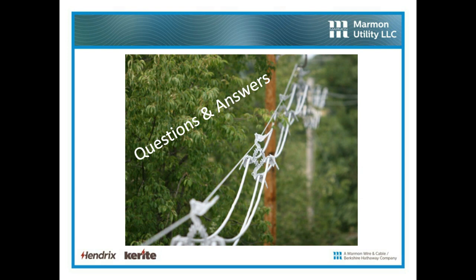Next question is, I've seen a tie wire cause the largest number of failures on bundled conductors. How has this been addressed with tie wire? With bare wire and covered conductor, I'd best have that one submitted in writing and give me a time to answer that. How has it been addressed? We basically introduced covered tie wire. We've always had covered tie wire. It's simple to use. Just don't use bare wire. And the second way that problem has been addressed is that utilities have simply gone to the vice top insulator. They don't have to worry about any tie wire anymore ever again. The covered conductor goes in the vice top. They turn the screws and they're done.